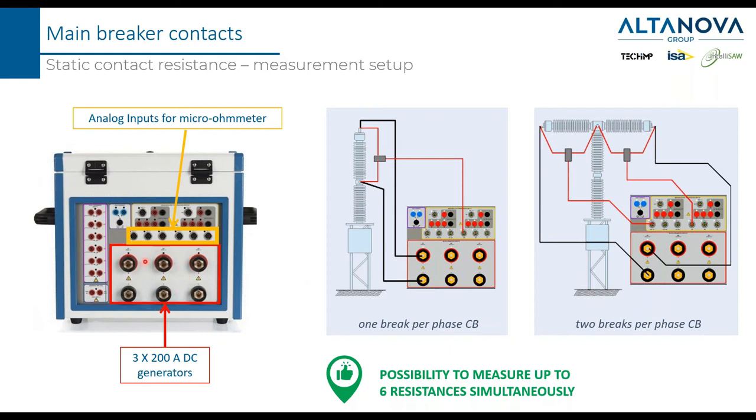The DC current generator in the CBA 3000 actually includes three generators — one per phase — 200 amps each. These are the voltage inputs for the resistance measurement. For a single-phase connection, the current flows through two current wires and the voltage is measured with two voltage wires — the four-wire method. For two breaks per phase, a similar connection is made. With a single connection, you can measure up to six resistances simultaneously, since there are three generators and six voltage inputs available.